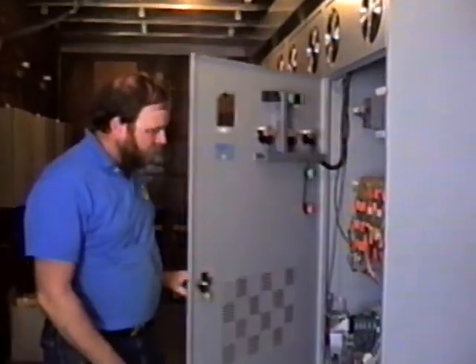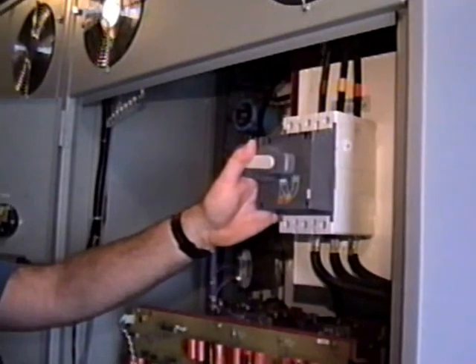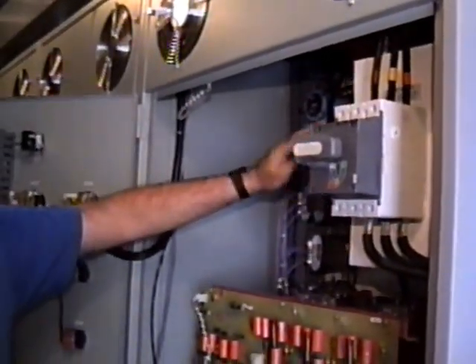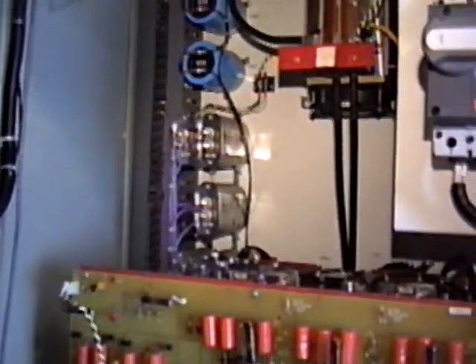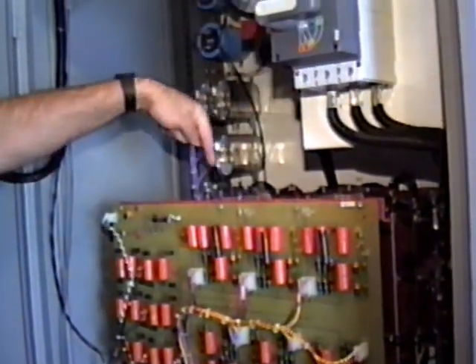This is the Robicon drive that I told you about, and here's what it looks like inside. We have 480-volt power that comes in through the circuit breaker here. It's then rectified to DC with the SCRs here. It passes through a very large inductor — the DC current passes through a big inductor down here — that keeps the DC current fairly constant even though we're switching it from one coil to the next. And then finally it goes to this inverter assembly, which is what actually puts the variable frequency, variable phase current out to the motors to make them run.